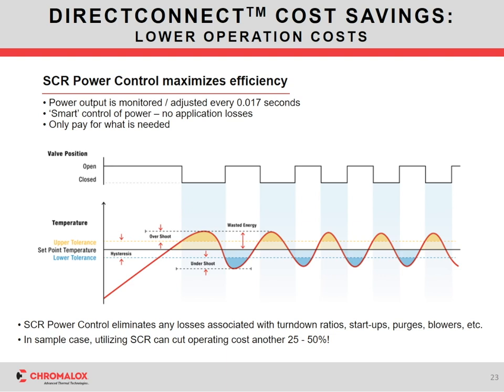And again, with an electrical heating system, you can have a controller in there that's able to learn from your process, so that you don't have large amounts of undershoot or overshoot. You can really tighten up on the deadband, so to speak, in such a process. And again, with the fossil fuel fired systems, that's not possible. You have turn down ratios, there's startups, there's purges that need to happen, there's blowers in the system that are just inherent to any fossil fuel fired system, where electric doesn't have that. And that's where having that SCR or thyristor control can cut your operating cost another 25 to 50%, and increase those savings over a traditional fossil fuel.